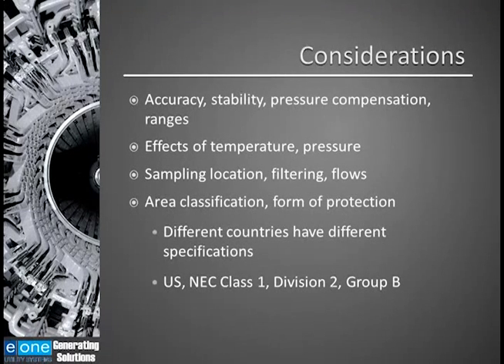You want to make sure that you're getting a good hydrogen flow so that you're getting a representative sample of that hydrogen. Again, because you're bringing hydrogen to this sensor, that area becomes a hazardous location. At a minimum, the sensor must be rated for use in a hazardous area, with the electronics in a safe area. I recommend, however, that the sensor and electronics both be rated to be used in a hazardous area.